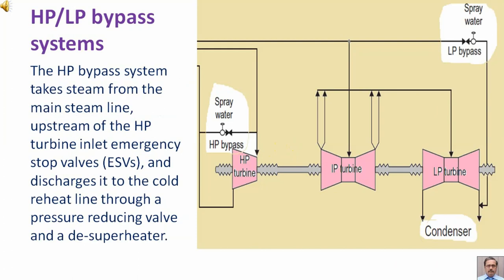HP bypass system takes steam from the main steam line, upstream of the HP turbine inlet emergency stop valve, and discharges it to the cold reheat line through a pressure reducing valve and a desuperheater.